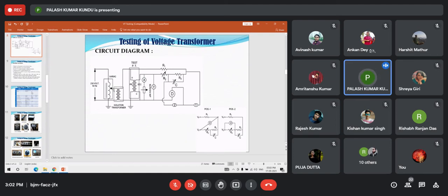So not only these variables, but there must also be a slight adjustment of the impedance, so that the product of the volt and the ampere remains constant at 25 VA, which is the standard burden condition. Because condition number 1 says the burden should be constant at 25 VA while varying the secondary voltage.